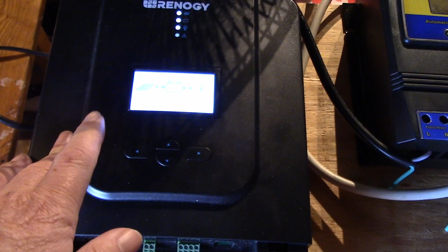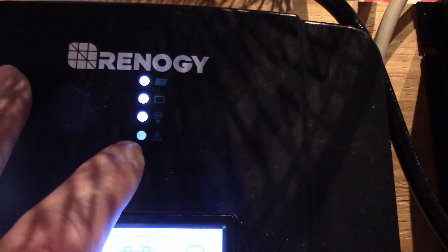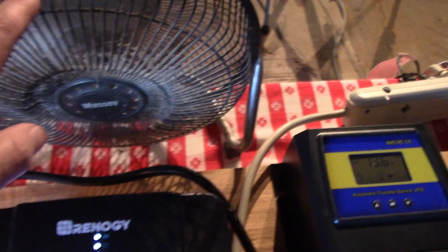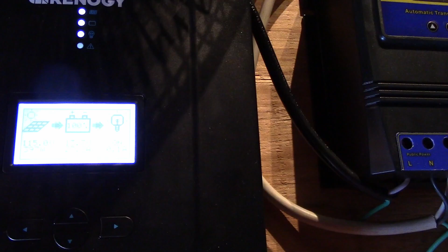So you're probably wondering why I have this fan sitting here. Well, this is designed to be mounted vertically on a piece of wood or cement fiberboard. I have it mounted horizontally, so warm air rises and the heat's been kind of building up here. It got up to 65°C, so I turned this fan on to keep the temperature down, and you can see it's at a much more reliable 32°C. So I was getting this little warning indicator here that it was too hot.